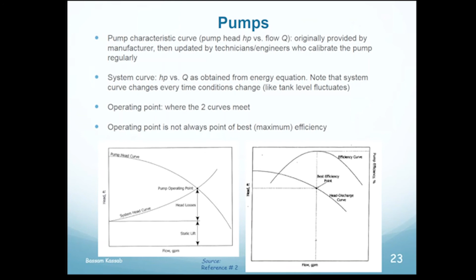Now, is it the most efficient point? Let's see. Well, you need to have an efficiency curve that you get from the manufacturer, or you find it yourself by doing some pump tests. And that's the efficiency curve that you can see on the right side here, pump efficiency. So ideally, you would like to run at the highest efficiency, but the operating point is not always the best efficiency point. If the operating point moves here, and if maximum efficiency is here, that means you are not running the pump at best efficiency. But you can't do much about that. You have to run the pump based on what the system needs. So it could sometimes be running at less than optimal efficiency.